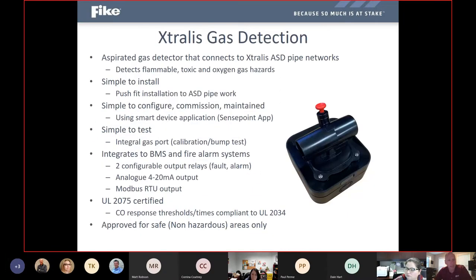One of the neat things about the air sampling system is that as we're pulling all that air to our unit, we can also put gas detection on those sampling pipes. So in some pretty heavy industrial areas where combustible, dangerous or toxic gases may be present, that we want to detect if there's ever an upset condition or if levels ever get to areas that might be dangerous for personnel or for operations, while we're pulling the gas in to sample it for smoke, we can also run it through a gas detection cartridge to sample it for potential presence of flammable or toxic gases. So it's very easy to install on those pipes to get basically two functions out of one unit, with both smoke detection and gas detection as well.